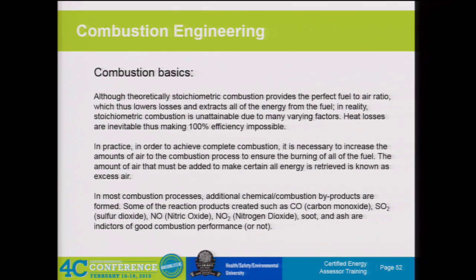We've been talking about excess air and measuring O2 in the stack. In practice, what happens in the firebox is that we're adding more air than what is required for perfect combustion to ensure we overcome the inefficiencies of the combustion process. There's a certain ignition loss or inefficiency just in getting the fuel ignited into the burner itself. We want to provide enough air so there are enough oxygen molecules to combust the fuel. As we monitor stack gases, we're looking for carbon monoxide—an incomplete conversion of carbon molecules. Instead of going to CO2, if we don't have enough air we get more CO, so that's an incomplete reaction.